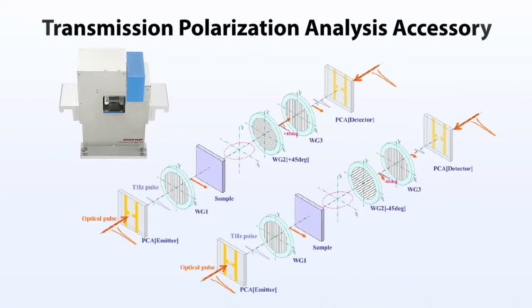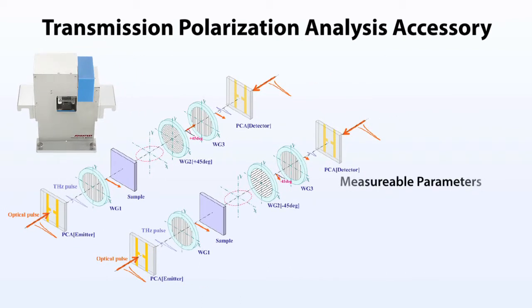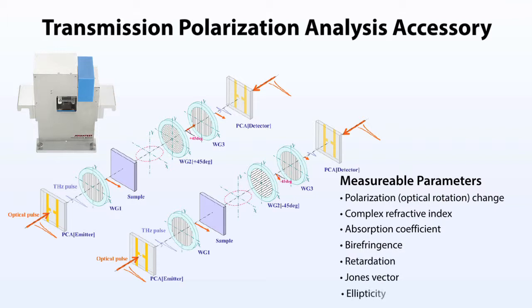The transmission polarization accessory uses a series of three linear polarizers to read out optical rotation angles. The first and the third polarizers are set to the polarization plane of the initial terahertz pulse. Optical rotation is measured by combining two sets of data obtained with plus 45 degree and minus 45 degree settings of the second polarizer.